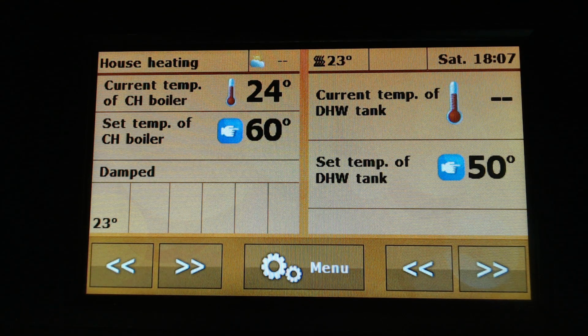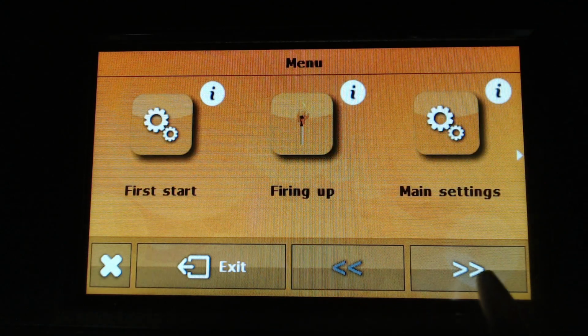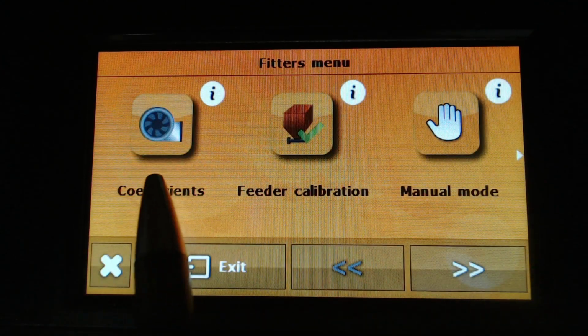As I said before, you cannot open the door fully, but you can open the door a little bit to check the flame. So open the door by, I don't know, 5-6 centimeters to see the flame inside, and if the combustion is all right, if the color of the flame is orange and the flame size is all right, then no problem, you can leave the boiler room without any adjustments. But if the flame is too small, too bright, let's say, or if the flame is too dark, too smoky, then you can adjust the flame inside the menu, fitters menu, coefficients.